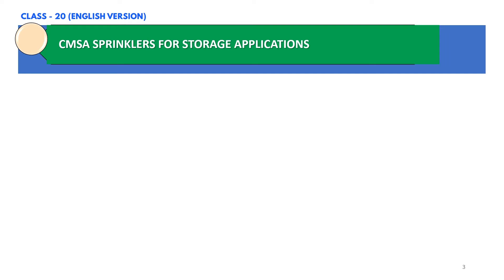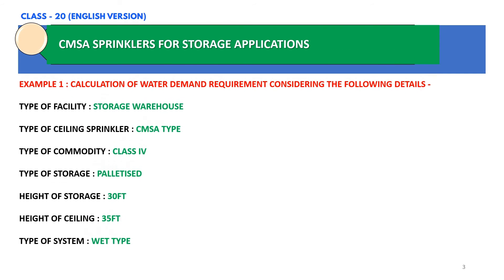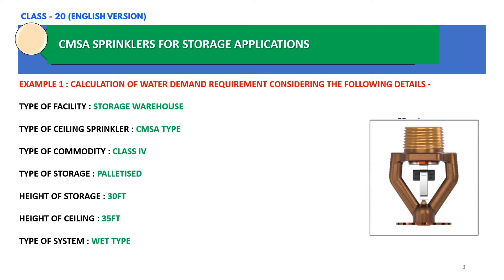In this slide, we are going to consider a storage warehouse example and try to find out the water demand requirement considering the details given. The type of facility is storage warehouse, type of ceiling sprinkler is CMSA type, type of commodity is class 4, type of storage is palletized storage, height of storage is 30 feet, height of ceiling is 35 feet, and type of system is wet type system.